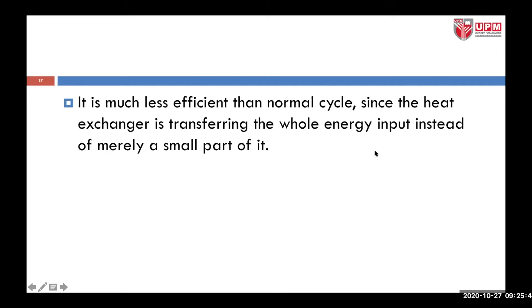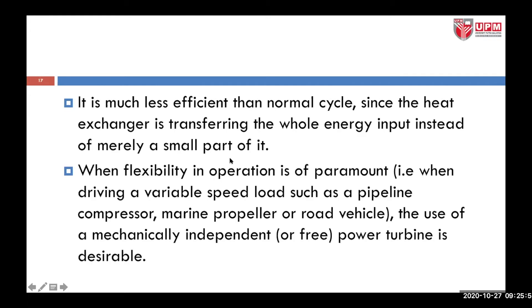This arrangement is much less efficient than the normal cycle since the heat exchanger is transferring the whole energy input instead of merely a small part of it. When flexibility in operation is of paramount importance — in other words, when driving a variable speed load such as a pipeline compressor, a marine propeller, or a road vehicle — the use of a mechanically independent or free power turbine is desirable, in contrast to the earlier fixed speed example.